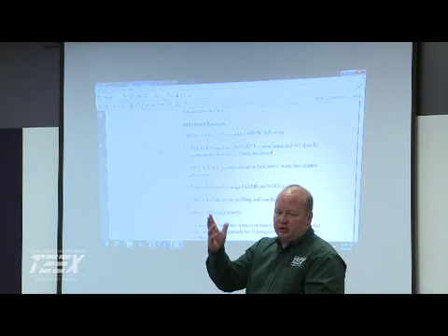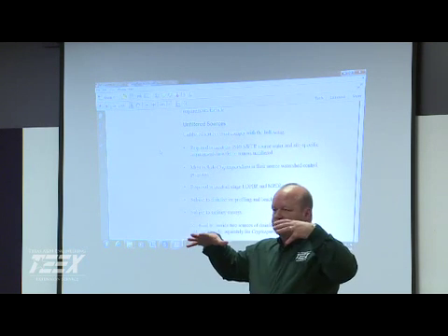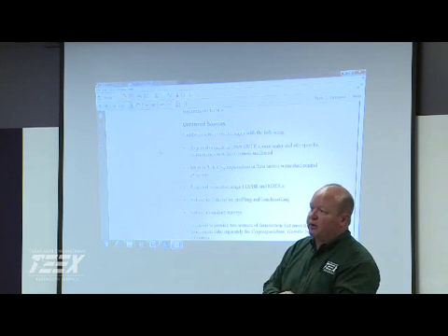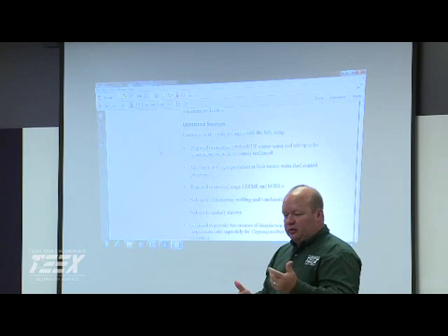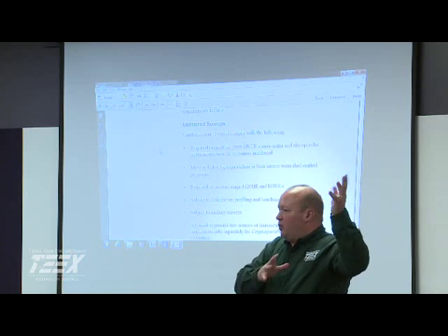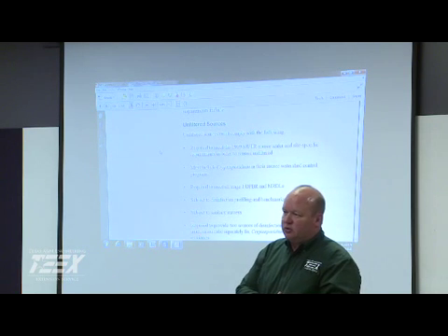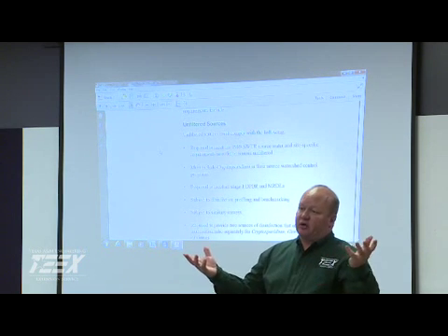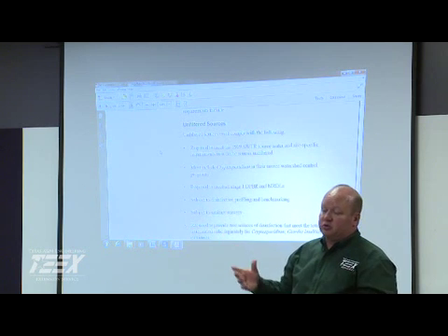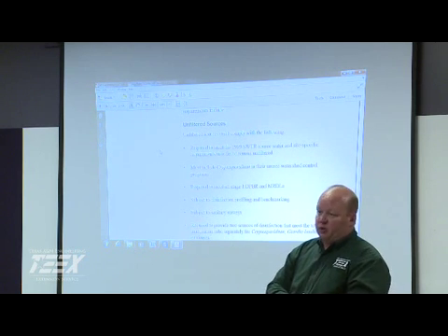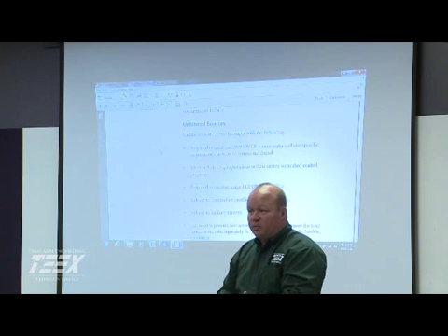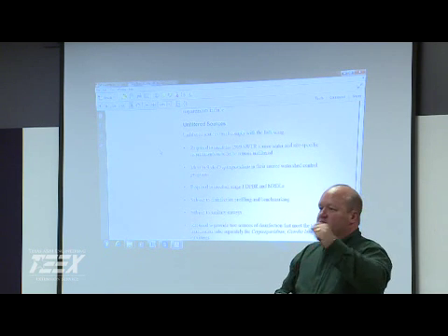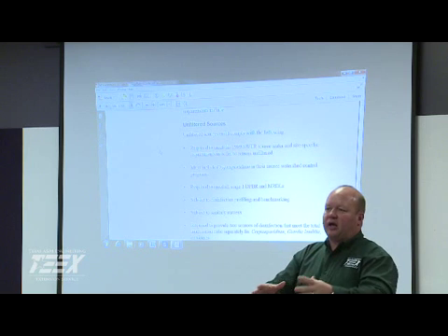Yeah. That was the thing with the Virgin Islands, they're using rain catchment systems, and everybody has cisterns, even the big businesses. We're talking about hospitals, everybody has these cisterns. And I'm thinking rainwater is squeaky clean, well, they're having a lot of disinfection byproducts. I'm like, well, they've got all the trees, basically tropical jungles around them, and they don't clean out their gutters. So they're making tea, organic tea, and then when they batch chlorinate, they put in such a huge amount. You've got localized, high concentration.